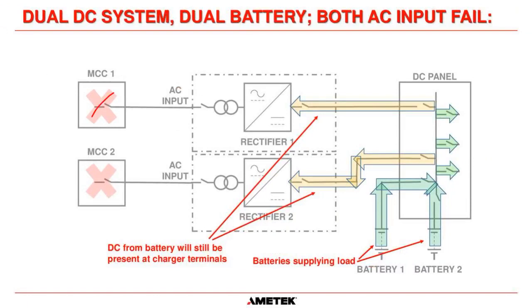Now, if we lose both MCCs, then what's going to happen is both batteries are going to take over and supply the load circuits. Okay? And once again, you're still going to have this back feed of the chargers. But both batteries will be sized in order for them to supply the load circuits with the correct current for the amount of time that's necessary.